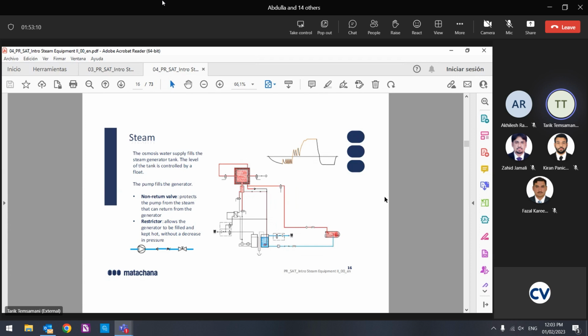So the circuit is easy. Water comes in here and we fill it. In the case of the 1000 machines, we have a triple switch for 3 levels: security level, minimum and maximum. Once we reach the maximum level, at this moment the heater starts working. If not, it stays off, for security.